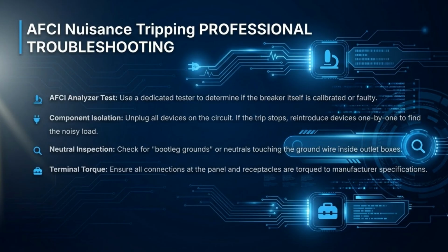The key professional troubleshooting steps include using an AFCI analyzer, isolating components to find the noisy load, inspecting neutrals for bootleg grounds, and ensuring terminal torque meets manufacturer specifications.